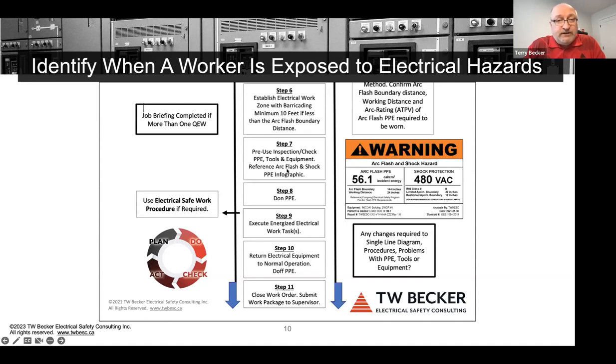And then the remaining workflow, like I said, once the worker gets these controls, they've got to field apply them. And again, we want them to formally set up a work zone and pre-use check the PPE. It's critical they pre-use check the electric shock PPE, specifically the rubber insulating gloves and leather protectors, and the AR PPE that they've determined that they need, that the employer obviously will support and assist them with respect to the provision of the PPE. And 70E and Z462 provide us, again, a toolbox of where we can get the information on what this PPE is that the employer might, and probably does, need to procure to provide to their workers.